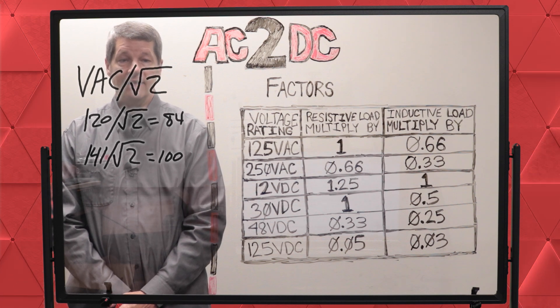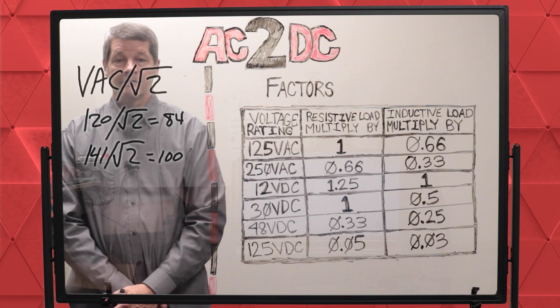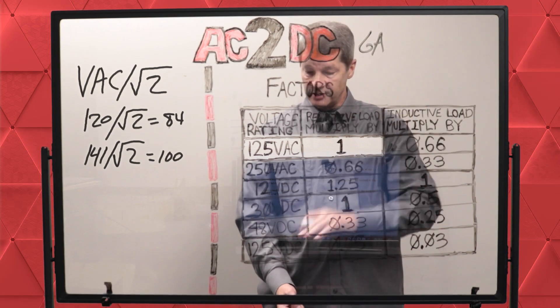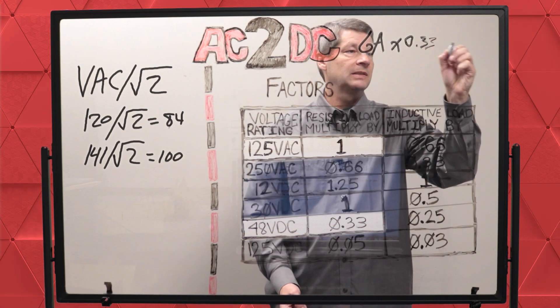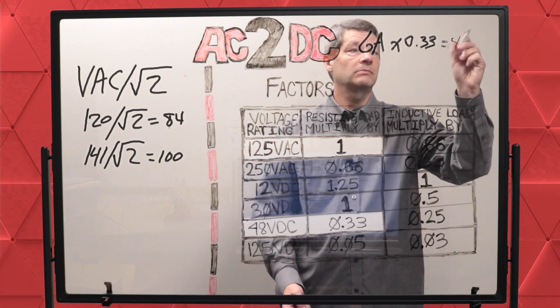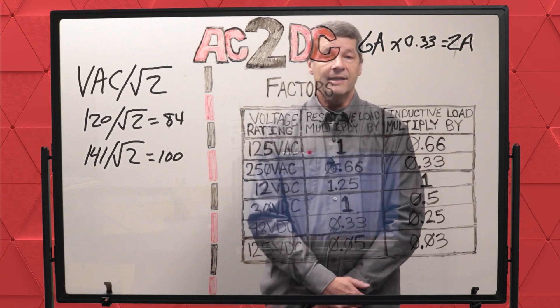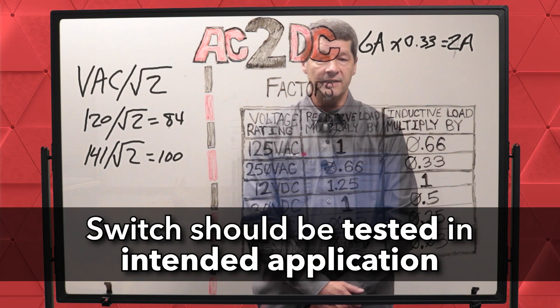The second method of converting AC to DC voltage is with the following factors in this chart. For example, if you have a switch rated for 6 amps at 125 volts AC and you want to use it at 48 volts DC, you would multiply it by 0.33, yielding 2 amps for your 48 volt DC circuit. Again, this is a mathematical re-rating and not tested data. The switch should be tested in the application in which it's intended to be used.